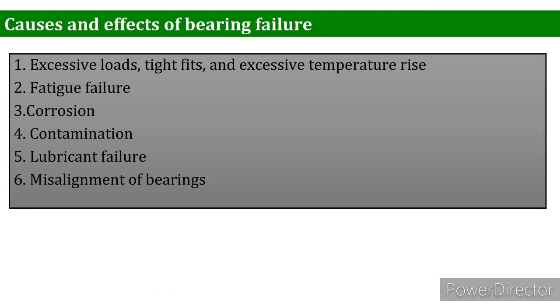Now there are some causes and effects of bearing failures which need to be discussed. The first one: excessive loads, tight fits and excessive temperature rise. All of these can anneal the races and the ball materials. They can also degrade, even destroy, the lubricants if the load exceeds the elastic limit of the bearing material. The second one is fatigue failure. This is due to the long run of bearings. It causes fracture and subsequent removal of small discrete particles of material from the surface of the races or balls. This type of bearing failure is progressive, that is, once initiated it will spread with further operation of the bearings. For this failure, the vibration and noise level of the motor will increase.